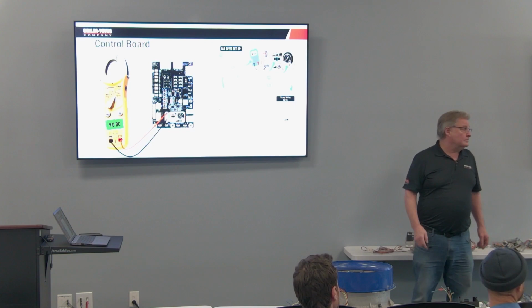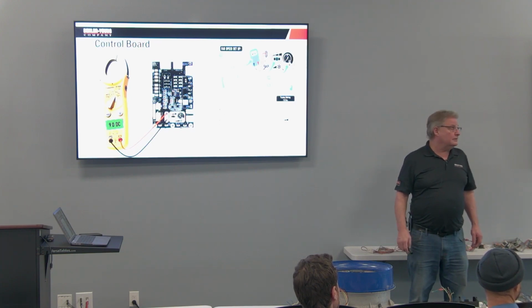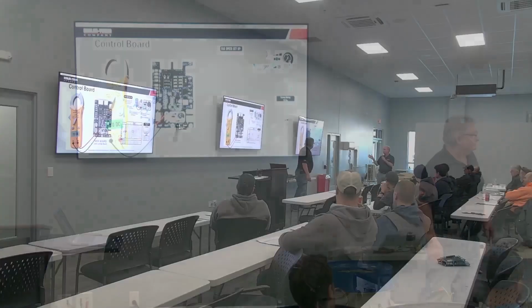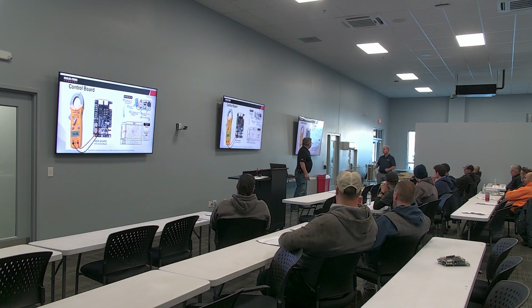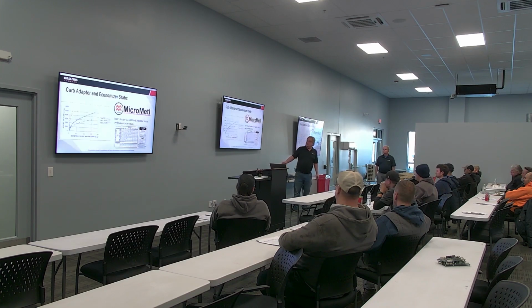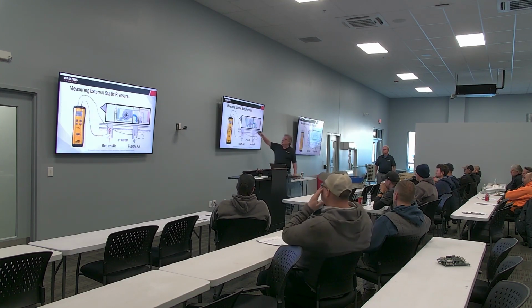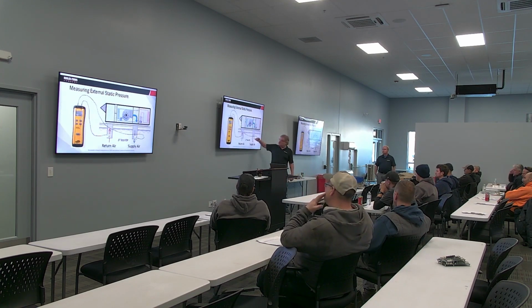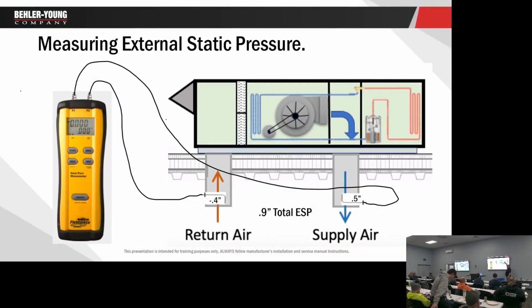I can hear people's brains saying, all right, well, if I'm measuring in the ductwork and I get 0.8 inches of static, do I have to consider the curb because I'm already measuring in the ductwork and isn't that showing me all of the static? That's a good question. And if we go back here, so the curb adapter, when we're measuring here, we're measuring from here down, right? We're not measuring back up here. So the curb adapter would be up here, just like the economizer's up here. So that's why we have to add them because we're measuring in the ductwork below the curb adapter.